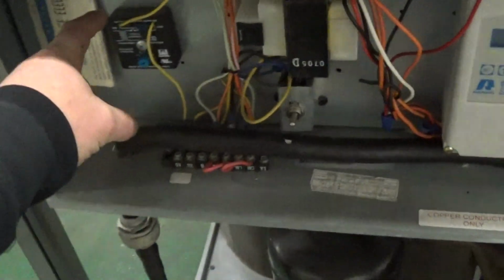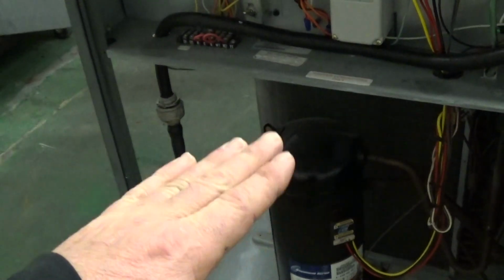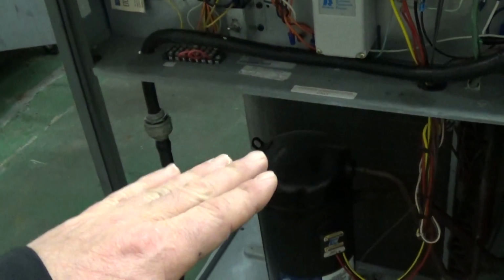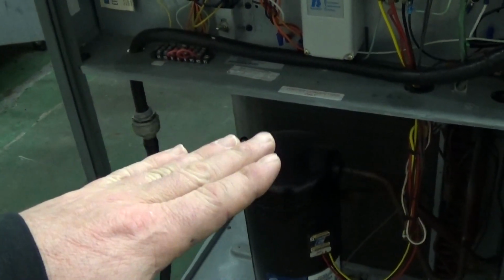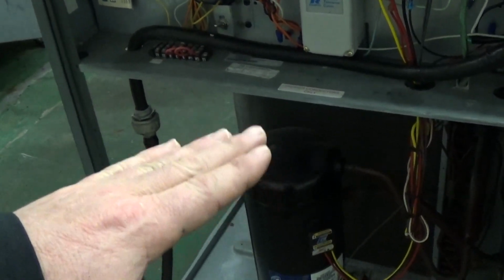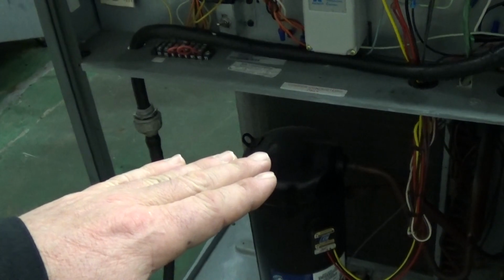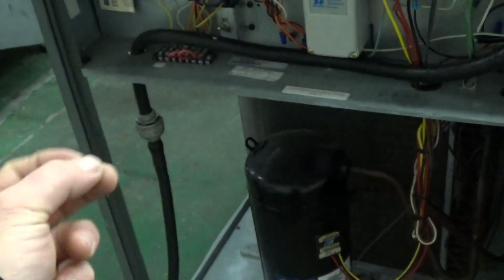The reason there's a delay timer in that is so when it gets to the hairy edge, and hopefully it never happens, but it's a safety. If it gets to the hairy edge where that switch is kind of just tapping on and off, you don't want the buzzer to be going on and off. You want to wait to a certain point where it's a steady signal.